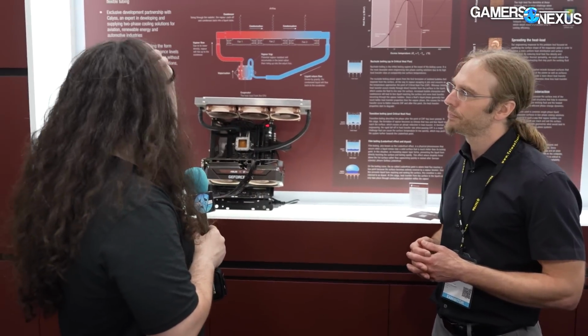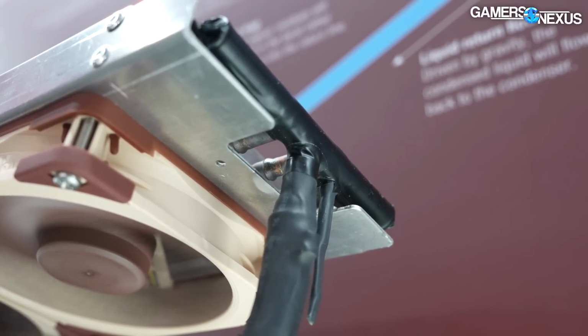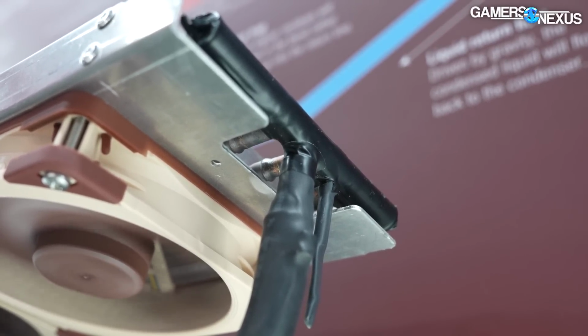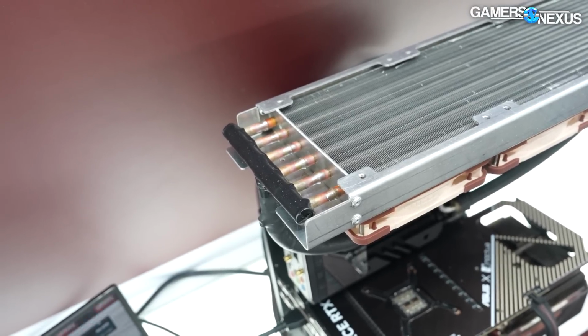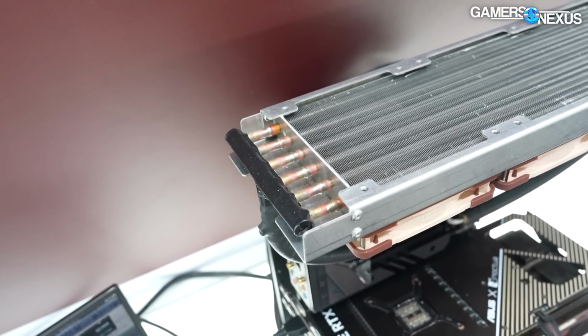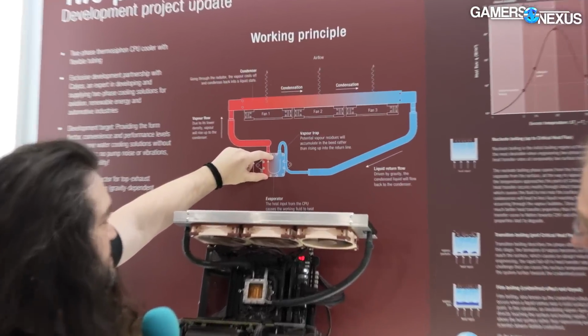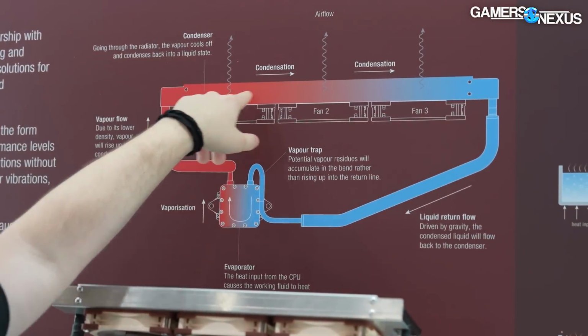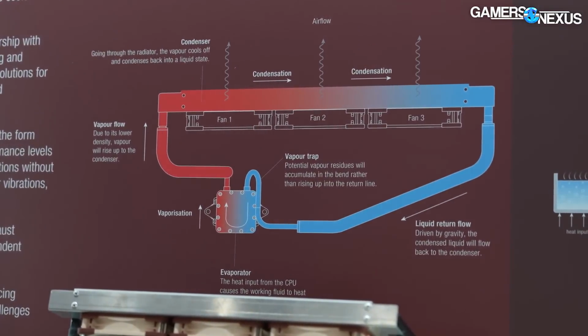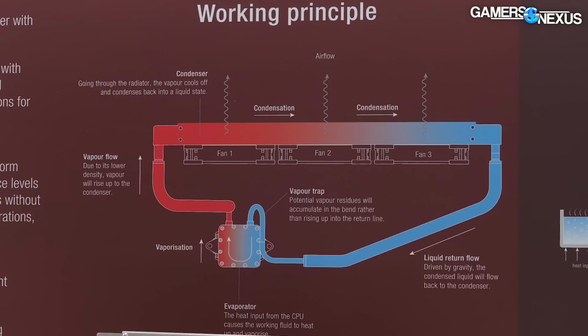Okay, and then Thermosiphon. Correct me if I get anything wrong before I hand it off to you, but my understanding is this can be thought of as two-phase, similar to a heat pipe, in that you have an evaporator and condenser cycle. As it evaporates at the heat source, it turns into a vapor, goes up, recondenses, comes down as a liquid, and does all of this in a pumpless fashion. There's no mechanical or electrical component to do the pumping of the liquid, and so no reliability component from the pump standpoint. Maybe from the liquid itself, permeation's a topic, but you're eliminating the pump itself. How else do you want to break down a thermosiphon at a top level?